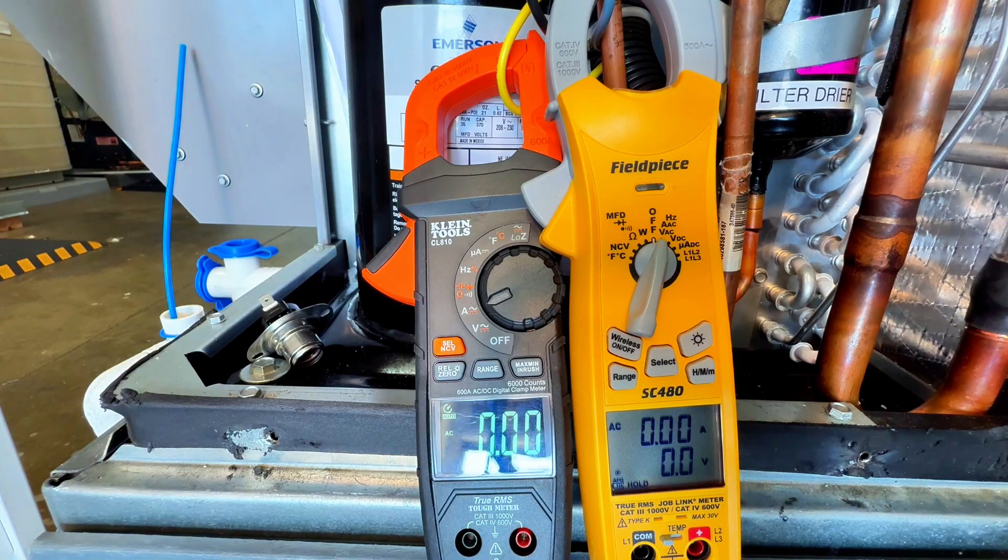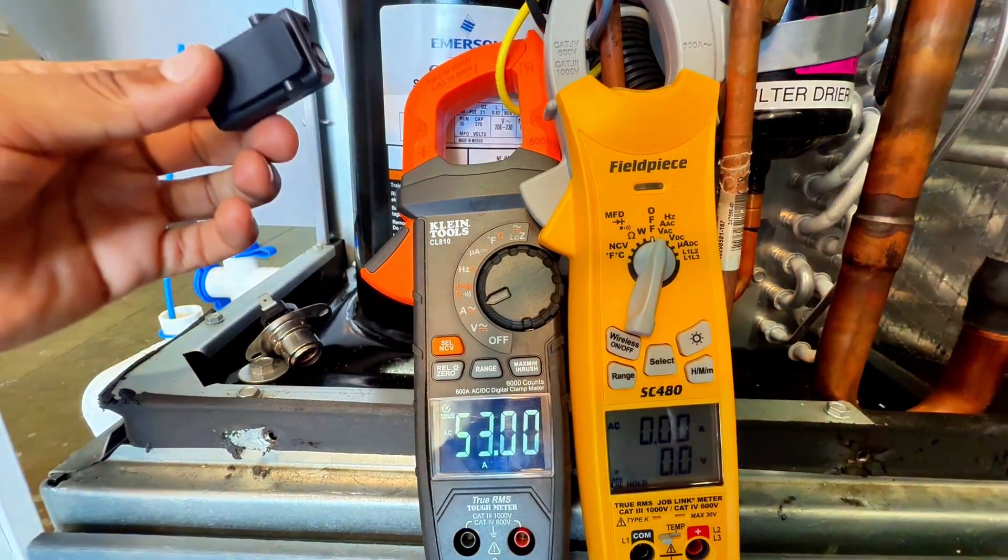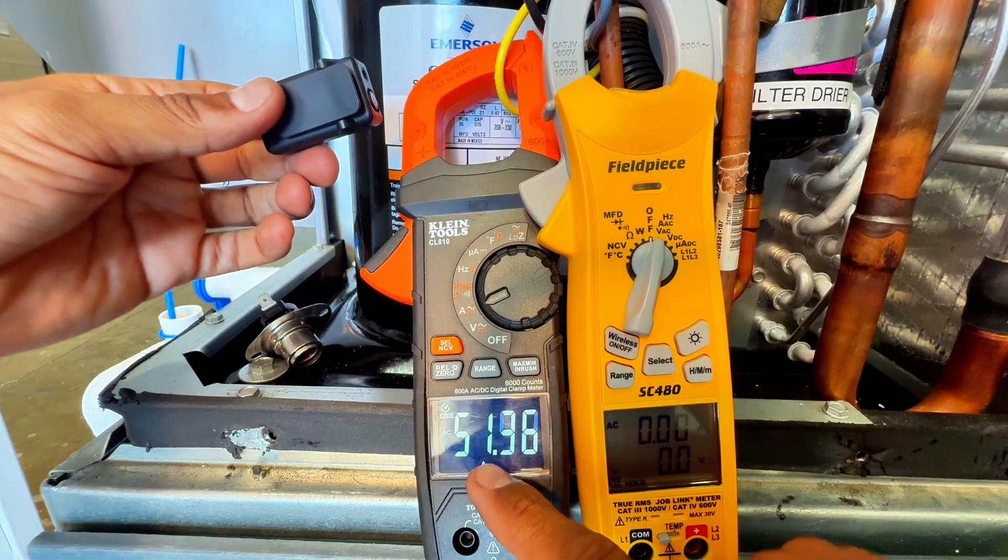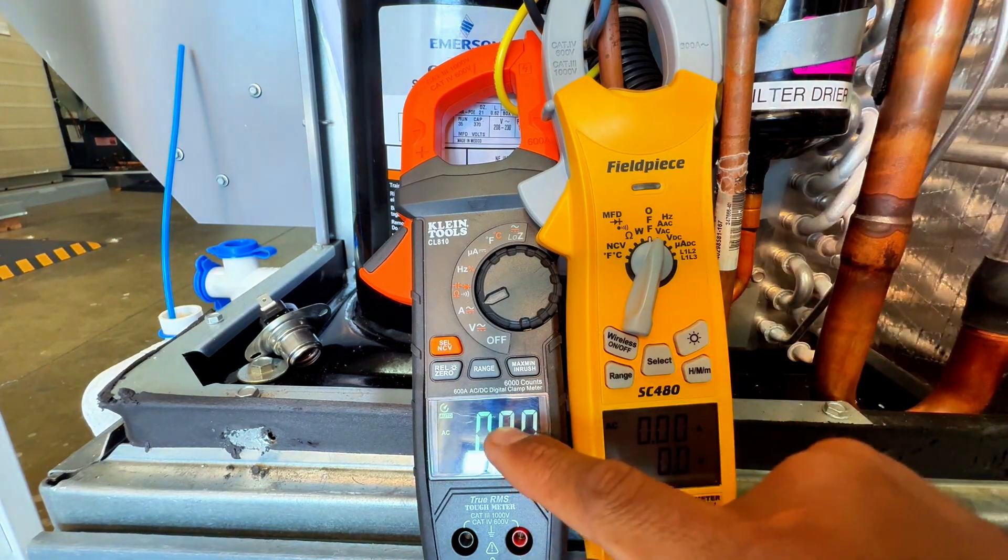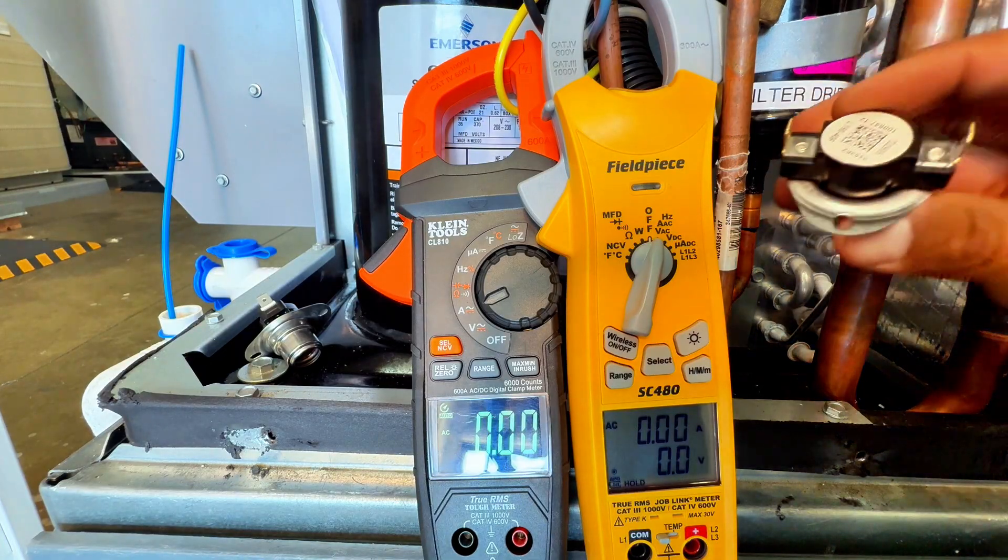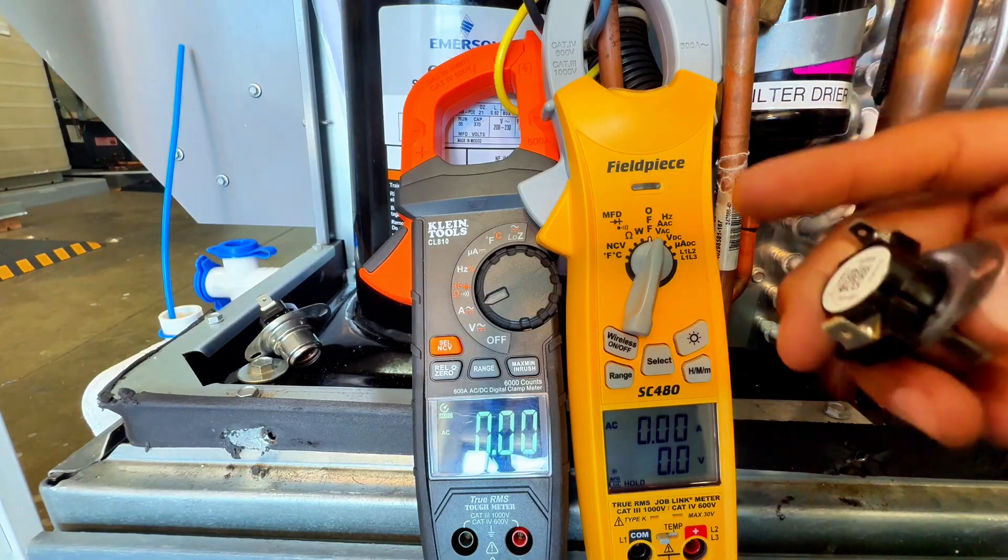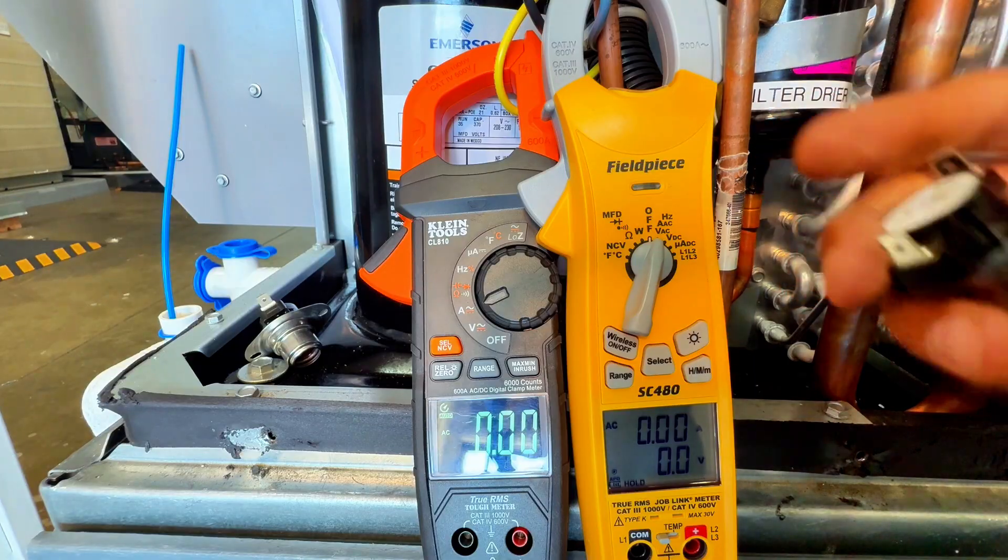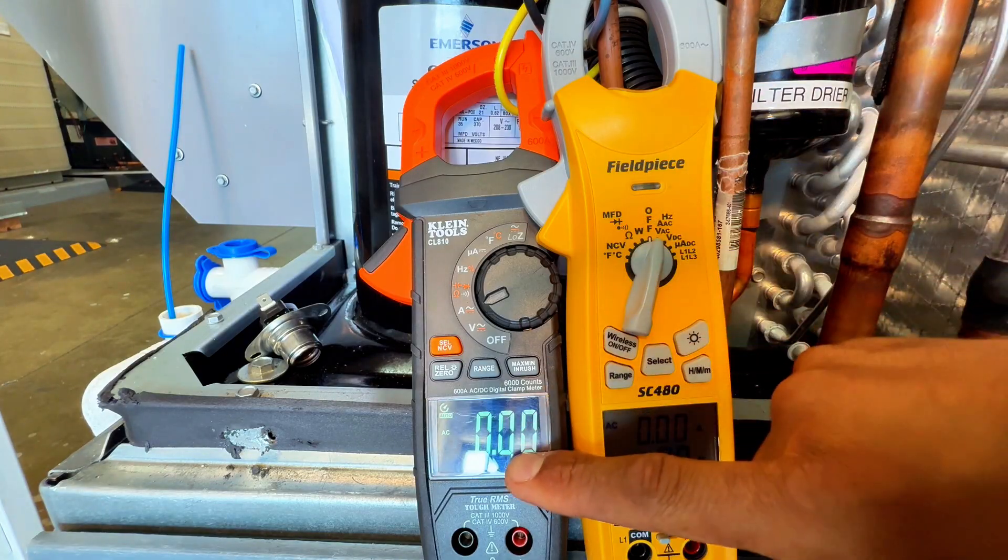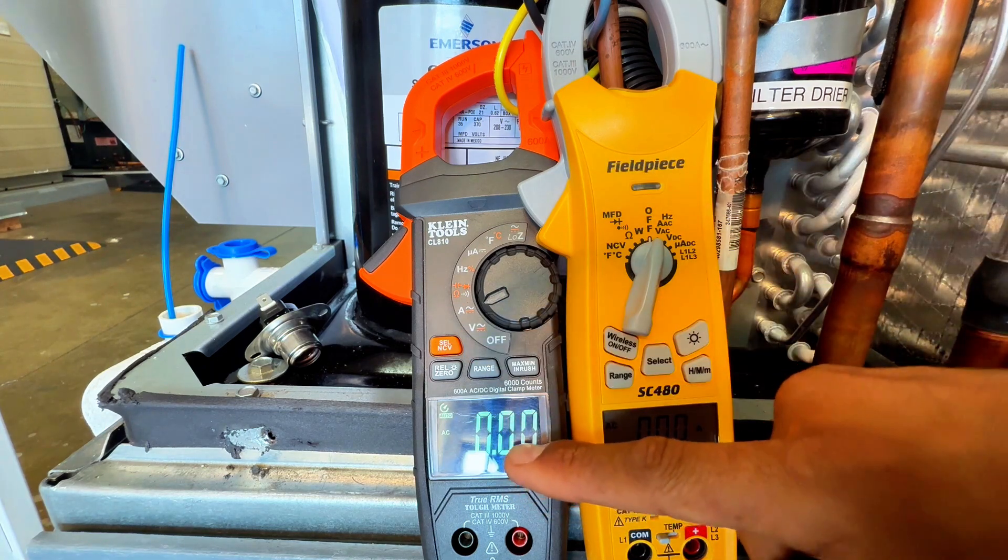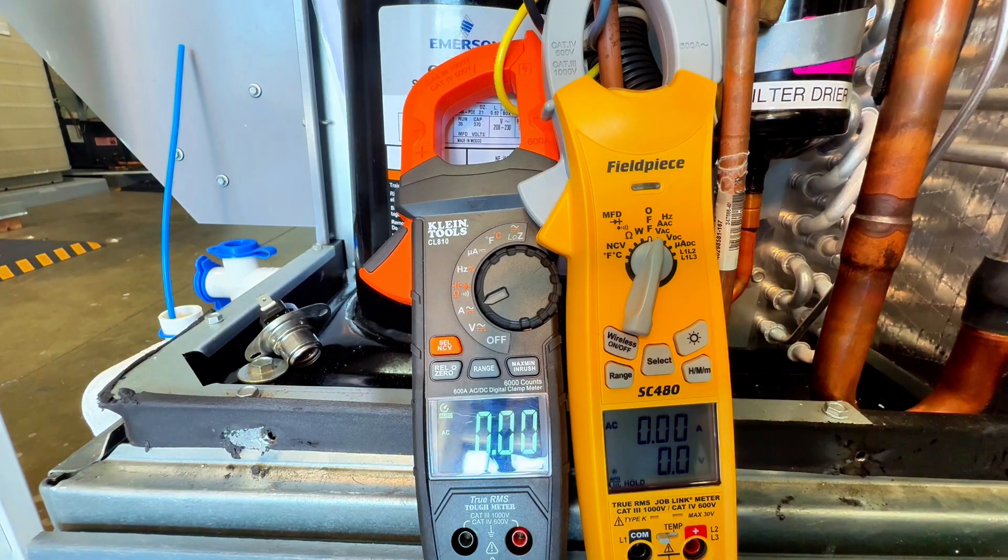Okay, so nothing has really changed besides the capacitor. But this one is on my run winding. Run winding. This is on my start winding. And I did put the bad cap. Of course, you always want this strapped. I'm just doing it for testing purposes. But you can tell it's a bad cap besides checking microfarads. You see it's a little swollen. So I put a bad cap. Okay, so coming back here, I'm going to go ahead and call and turn on the compressor. I'm going to get my actual mic so you can hear the noise the compressor makes like a humming noise. But I also want you to pay attention to these two numbers. So run winding and start winding. So let me go ahead and call for cooling. And I'm going to go ahead and get that mic and put it right next to the compressor so you can hear. Okay, did you see that? It was humming pretty loud and it was pulling a lot of current and then boom, it went to zero. It went to zero because the thermal overload opened.